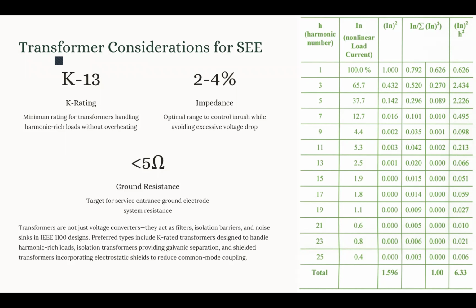I mentioned those ratings and values of nonlinear load currents in the table that you see in the slide. A higher K rating, like 20 or 30, could be recommended for extreme harmonic conditions. This is important because a non-K-rated transformer will overheat and fail permanently when we have a harmonic-rich condition.